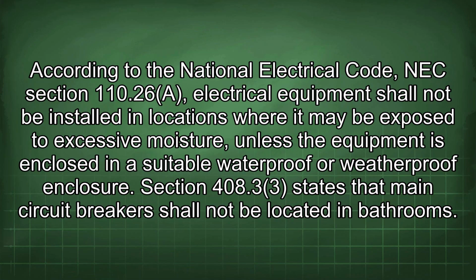According to the National Electrical Code, NEC Section 110.26(A), electrical equipment shall not be installed in locations where it may be exposed to excessive moisture unless the equipment is enclosed in a suitable waterproof or weatherproof enclosure. Section 408.3(3) states that main circuit breakers shall not be located in bathrooms.